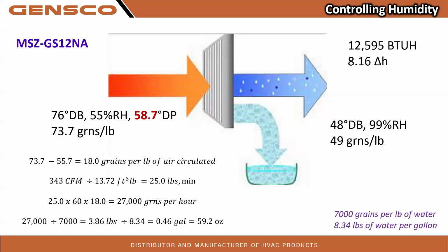So if we take the difference, 73.7 and 55, we have 18 grains per pound of air removed after we have done dehumidification. And I got my number wrong over there. That was 55.7. And this particular unit, a GS12, 343 CFM with a wet coil, is circulating at that condition, 76 and 55%. It occupies a volume of 13.72 cubic feet per pound of air. That would equal 25 pounds of air circulating per minute.